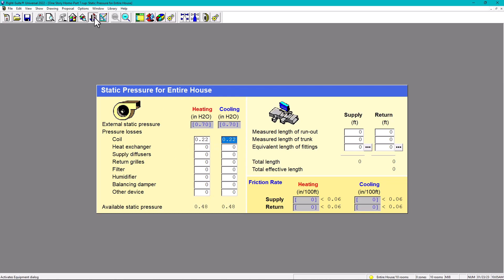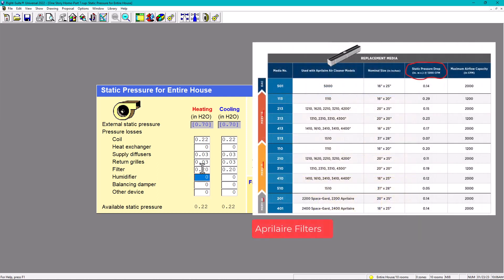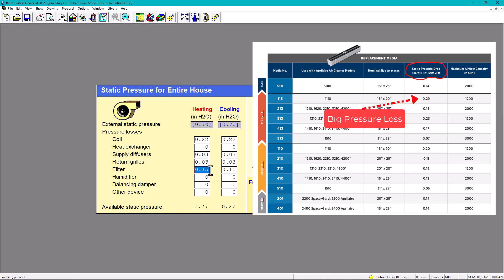For the heat exchanger, since this is a gas furnace, the heat exchanger loss is already accounted for in the 0.70, so we're going to put zero. Now for supply and return grills, we're going to put 0.03 as Manual D suggests. Then 0.03 for returns. For filter, that depends on each case. If you want a thicker, high-efficiency filter, you're going to have a bigger pressure loss, say 0.2. If you have a basic filter, the pressure loss is 0.10. So let's put an average of 0.15.